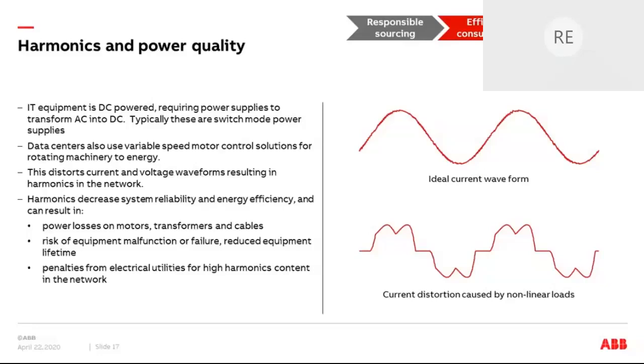This can be very impactful for a data center, because if you have a lot of harmonics content, utilities will charge you extra for supplying that type of power. There's a power quality charge, typically called a power factor charge, and it can really affect your bill and your spend on electrical. If we can find a more efficient way to do this, simple things like using more up-to-date power supplies can make an impact.